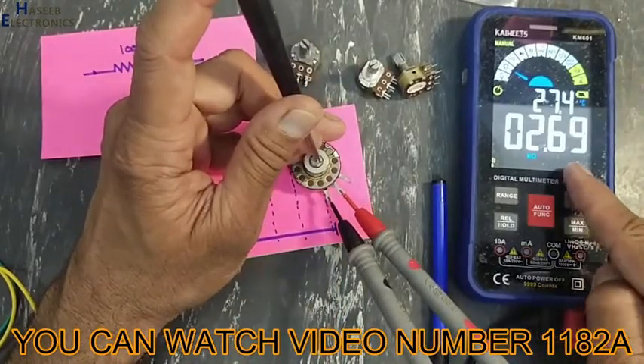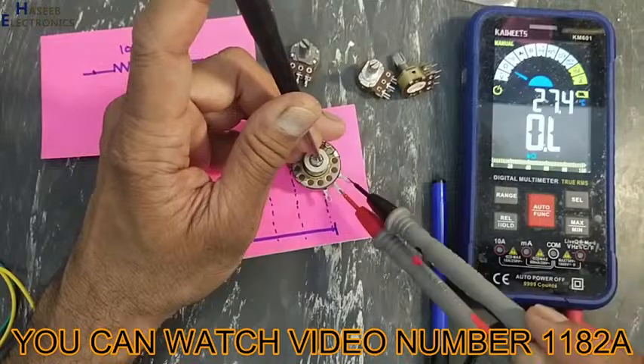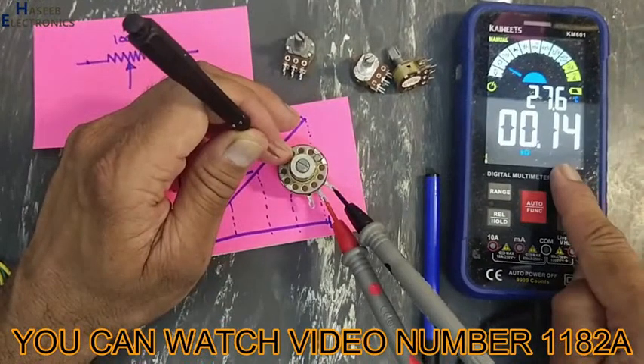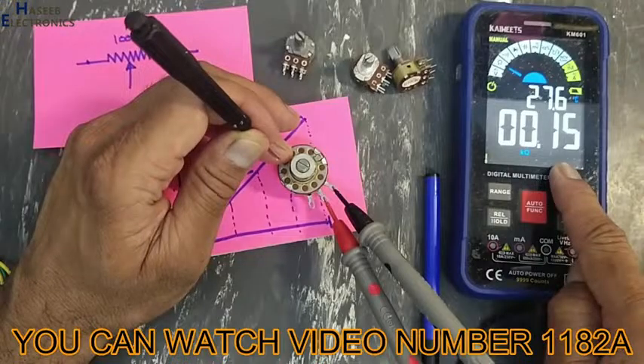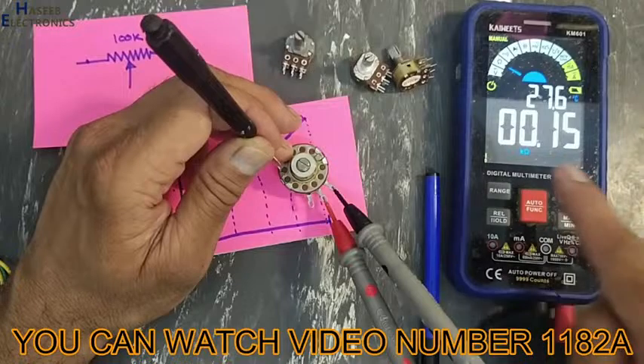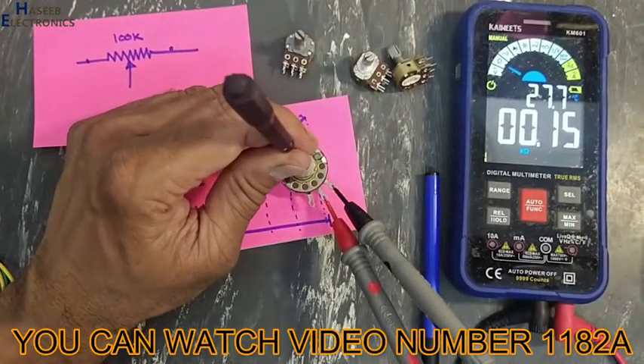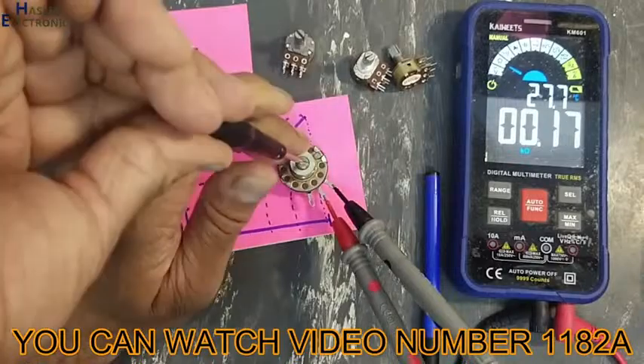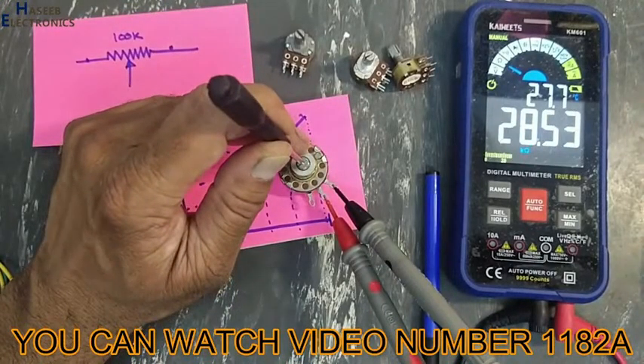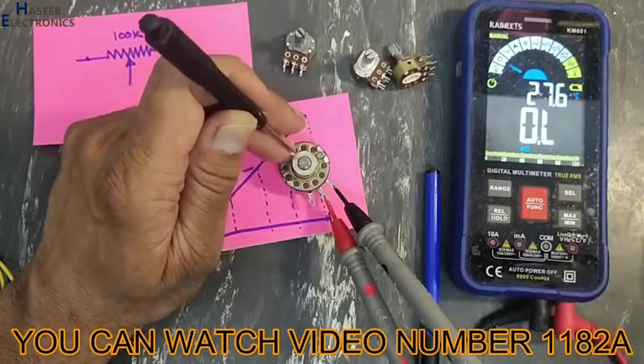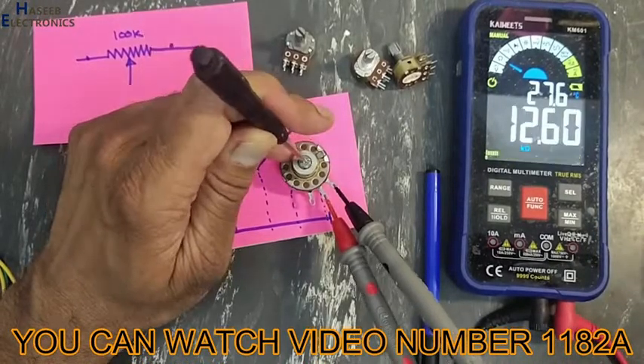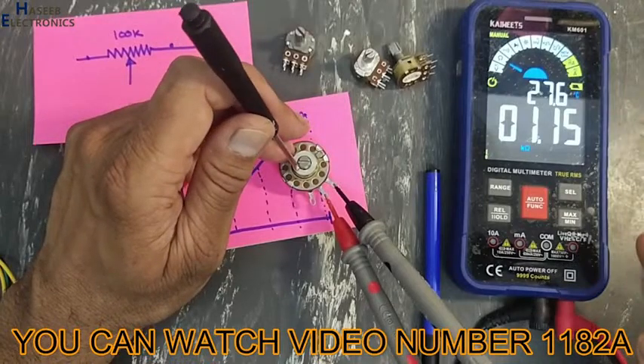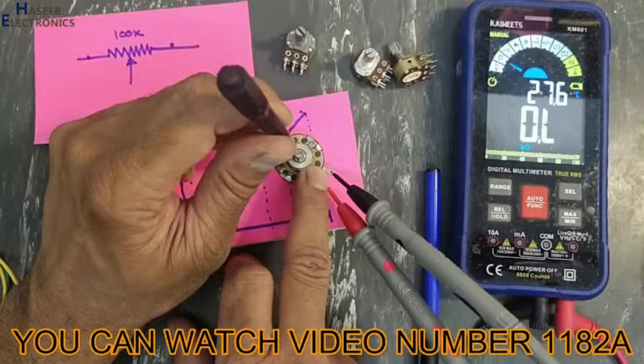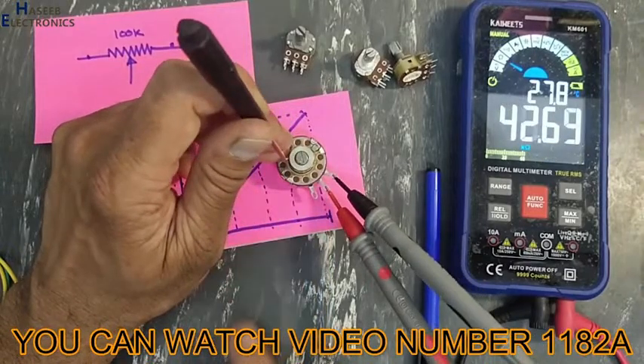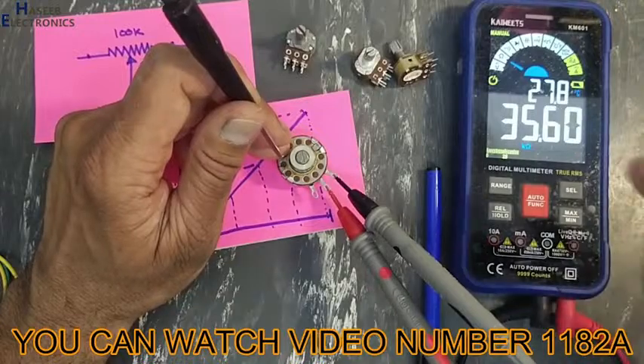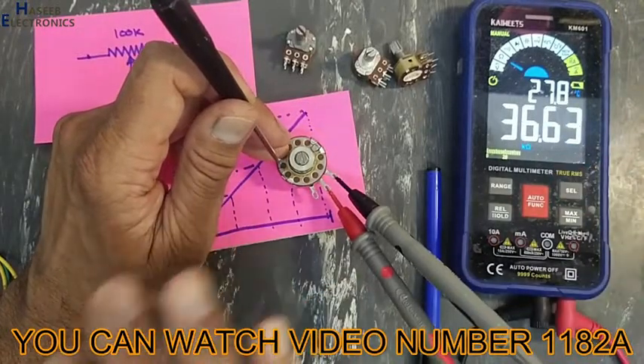Here it is showing 2.69K on one side. If I test between these two terminals in the full clockwise position, it shows some resistance, 0.15K, or 150 ohms. Now if I rotate it counterclockwise, we can see its resistance is increasing. Sometimes it is disconnected, showing 1.1K, then 44K, 33K. So this potentiometer's linearity test is failed.